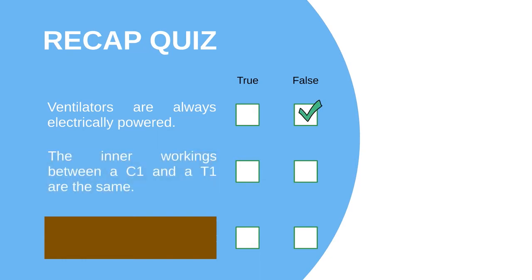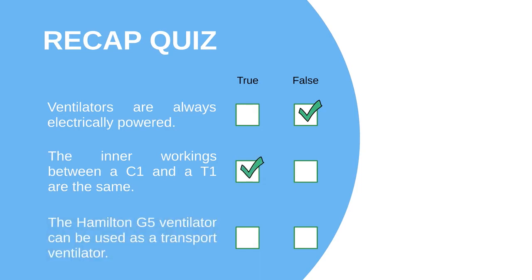Quick recap quiz: Ventilators are always electrically powered — that is false. The inner workings between the C1 and the T1 ventilator are the same — that is true. The Hamilton G5 ventilator can be used as a transport ventilator — that is false.